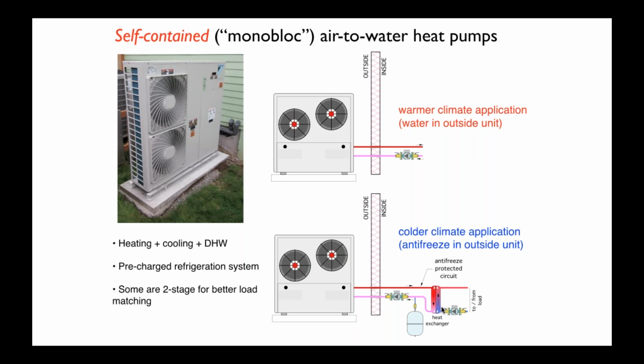You will get a performance penalty when you put a heat exchanger in, because you have to have a temperature difference to drive heat from the heat pump side to the system side. How much of a temperature difference depends on how large that heat exchanger is. But one of the cardinal rules, and again, we'll talk about it more today and emphasize it in part 2, you want to keep that heat pump running at the lowest water temperature or the lowest fluid temperature possible. That's where you're going to get the best efficiency. So anything you can do on the system side to bring that water temperature down is going to be to your advantage. So honestly, I've done systems both ways. I prefer to use antifreeze through the entire system today if it is a monoblock heat pump that we're working with, rather than put the heat exchanger in. The other aspect of the heat exchanger, you're going to need 2 circulators. So you'll have a higher installed cost. You also have a higher operating cost.